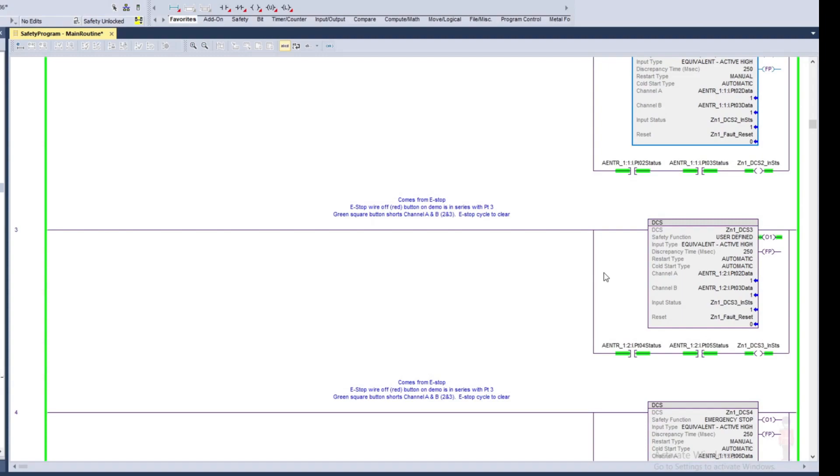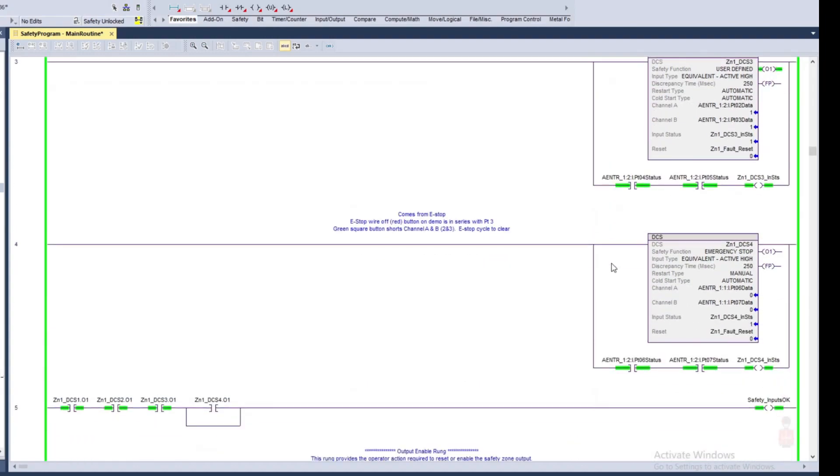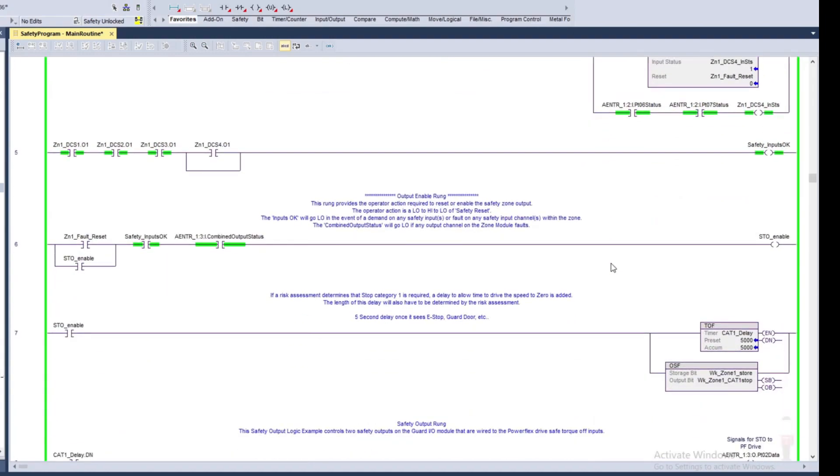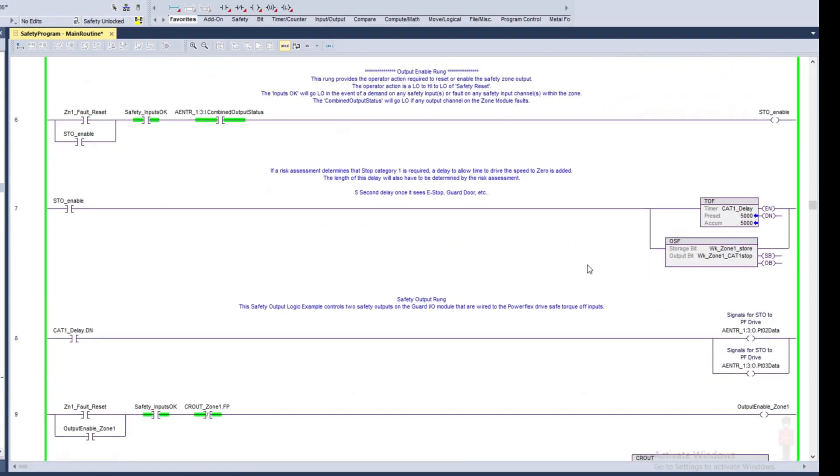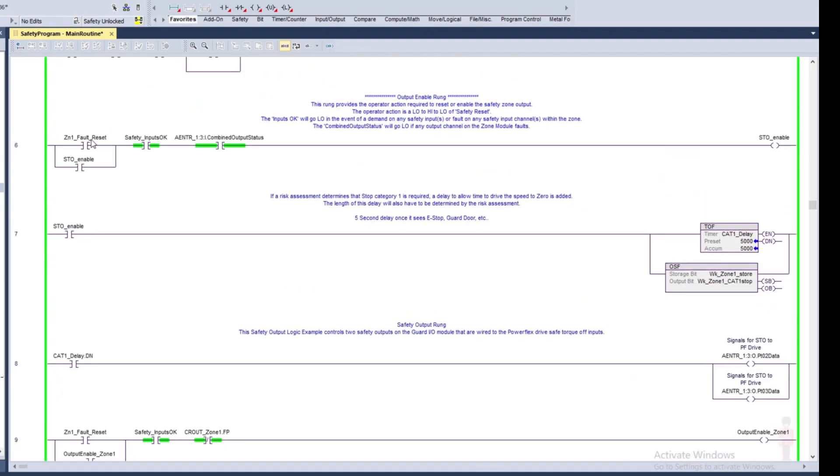Now I pull the e-stop. Notice my DCS instruction now, output one goes high because it's functioning just fine. However, after an e-stop I need to turn on my reset again. I have to reset the circuit, restart the outputs, because anytime you hit a DCS you don't want to just pull the DCS and have the machine just start running automatically again.